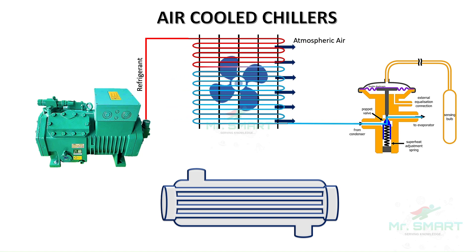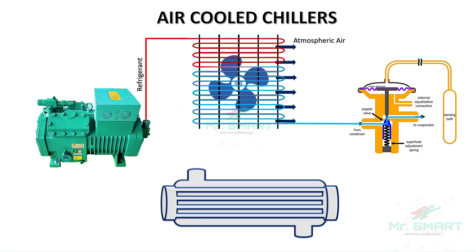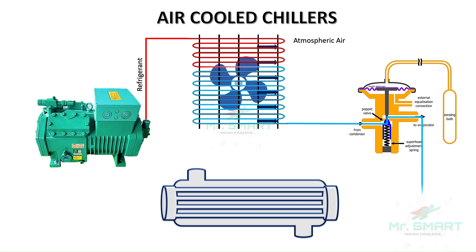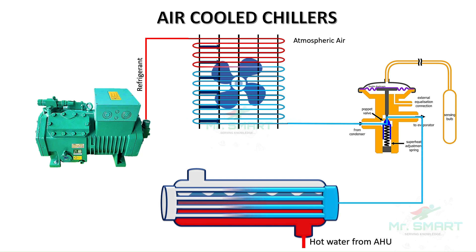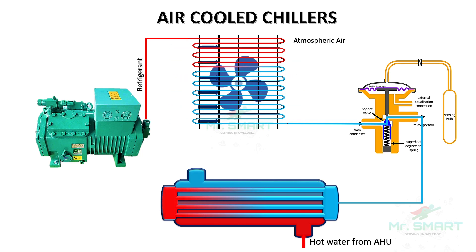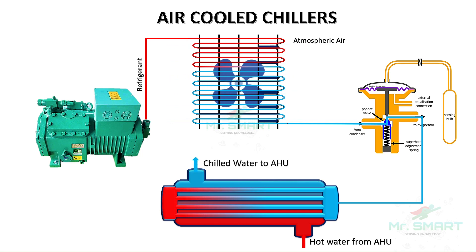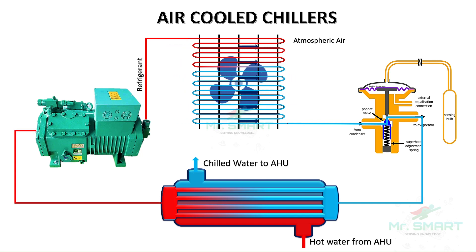The high-pressure liquid after condensation is passed through the expansion valve, which reduces the pressure and temperature of the refrigerant before it enters the evaporator. In the evaporator, the refrigerant absorbs heat from the hot water released from the AHU, evaporating into a low-pressure refrigerant. This low-pressure refrigerant is then compressed again, and the cycle repeats.